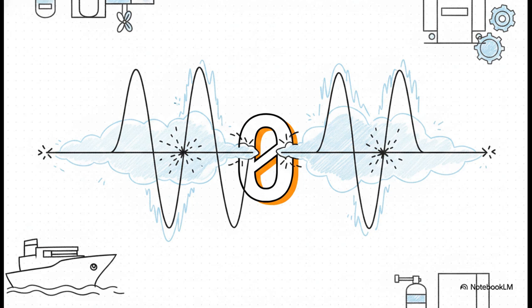Because marine grids use alternating current, the electrical waveform naturally drops to 0 volts and 0 amps 50 or 60 times every single second as it reverses direction. At that exact microsecond, at the current zero crossing, the arc naturally extinguishes itself just because there's momentarily no energy feeding it. And here is the ultimate climax of our whole explainer. Every single medium voltage breaker technology on Earth, whether it uses vacuum bottles, SF6 gas, or air chutes, exists for one singular purpose. It is designed to rapidly flush the space between the contacts with insulation so that when that natural zero crossing happens, the kill is made permanent. It stops the arc from restriking when the voltage waveform rises again just a millisecond later.